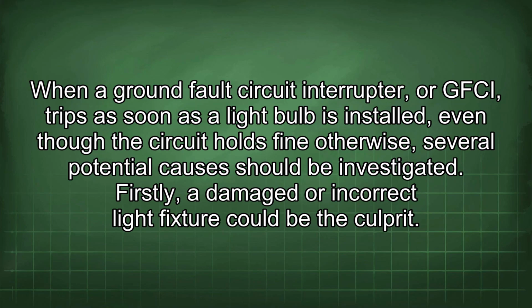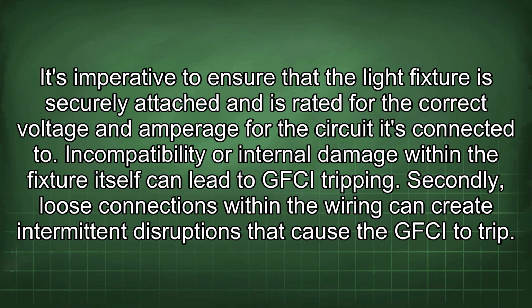When a ground fault circuit interrupter, or GFCI, trips as soon as the light bulb is installed, even though the circuit holds fine otherwise, several potential causes should be investigated. Firstly, a damaged or incorrect light fixture could be the culprit. It's imperative to ensure that the light fixture is securely attached and is rated for the correct voltage and amperage for the circuit it's connected to. Incompatibility or internal damage within the fixture itself can lead to GFCI tripping.